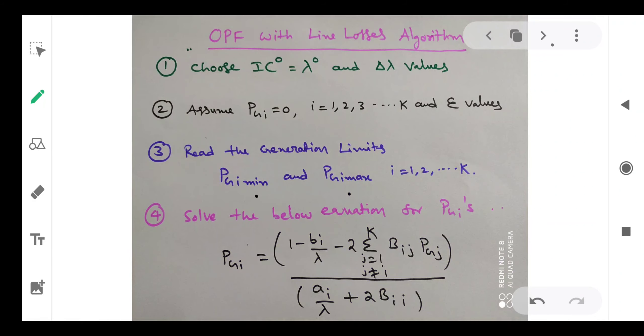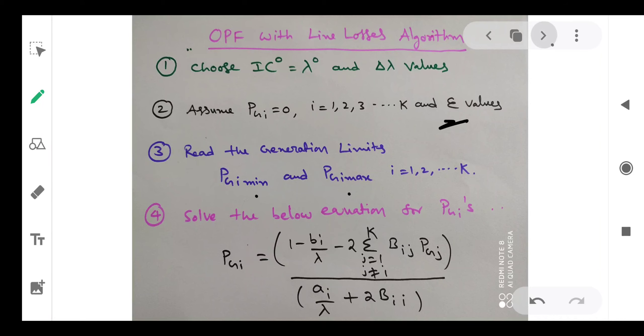Once again, a review of the algorithm. In the algorithm, first of all we need to choose IC0, lambda0, and delta lambda values. Delta lambda value is useful in the iterative solution to increase or decrease lambda to get the appropriate solution. Second: assume PGi initial generations are equal to zero, from i equal to 1 to K, and choose the epsilon tolerance value. Third: read the generation limits — PGi minimum and PGi maximum — for all units or generating plants. Now solve the equation for PGi in terms of Bij.